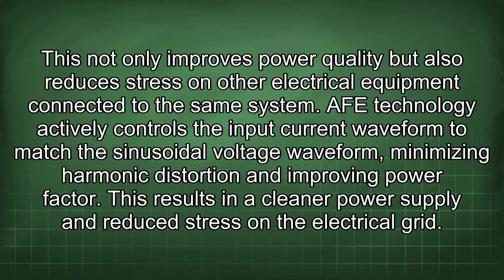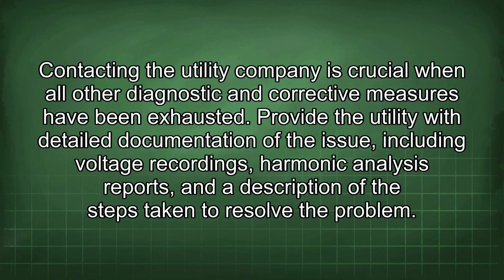AFE technology actively controls the input current waveform to match the sinusoidal voltage waveform, minimizing harmonic distortion and improving power factor. This results in a cleaner power supply and reduced stress on the electrical grid. Contacting the utility company is crucial when all other diagnostic and corrective measures have been exhausted. Provide the utility with detailed documentation of the issue, including voltage recordings, harmonic analysis reports, and a description of the steps taken to resolve the problem.